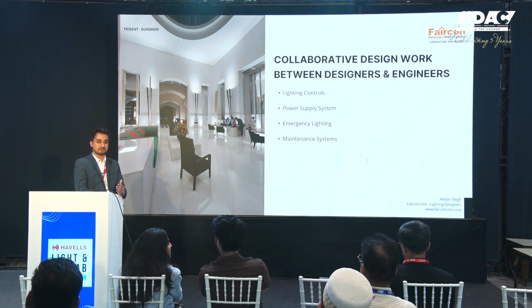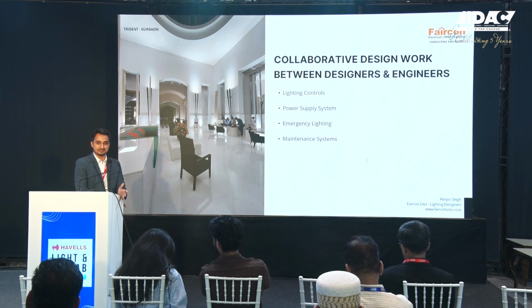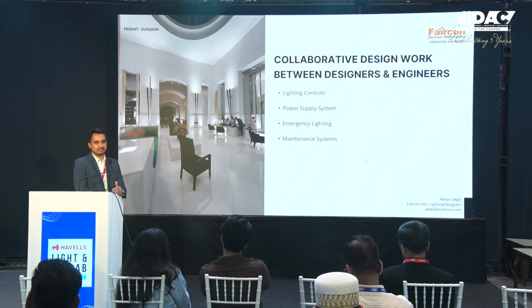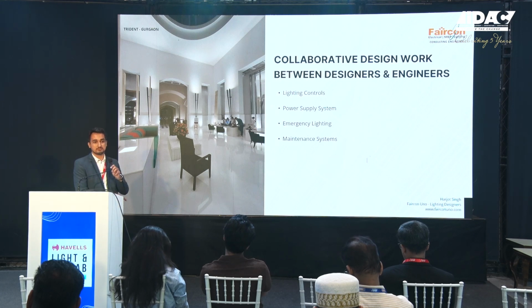At the same time, you're not aware of the quality of power that is being provided. Will your fixtures be able to sustain over a long period of time? Do you need a UPS? Do you need surge protection? That is where the engineering team comes in. Information has to travel back and forth between the two, because in contemporary designs, maintenance is a big issue. With these ceiling heights, it's not easy to keep changing light fixtures every month or so. So it is important that the engineering team provides the correct protections and distributions, with load balanced, so you don't have fixtures burning out because the distribution is not done correctly.